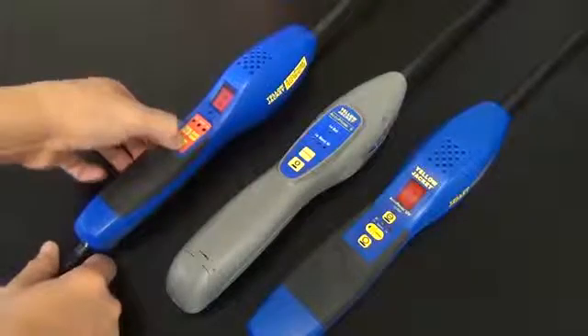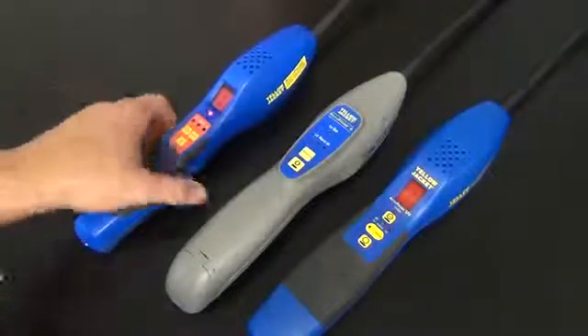So again, if your sensor is not pushed on all the way or it's on incorrectly, when you try to turn on the leak detector, it will not turn on. Take the sensor off, double check your alignment and orientation, and make sure it's pushed down all the way.